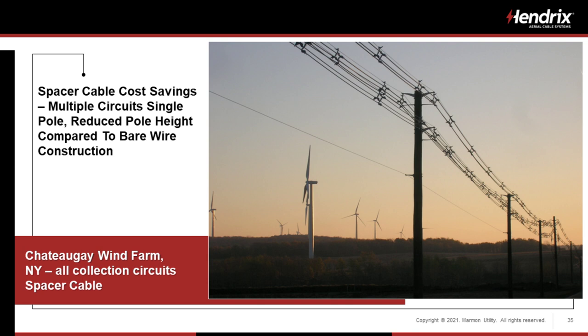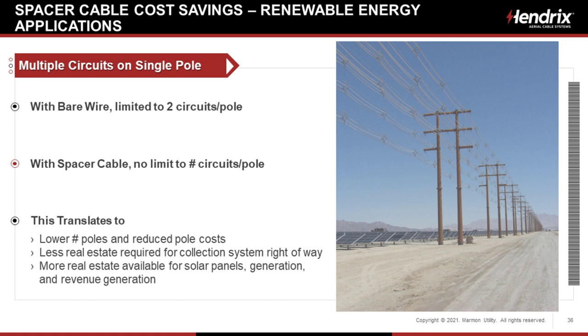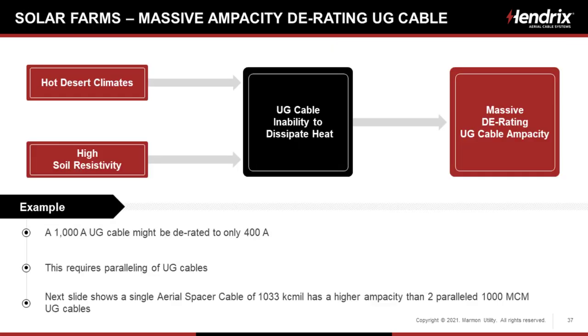Compare that to what we're doing. We put the same three circuits on a pole, probably less robust, and we've never had a problem with that, and it's very low profile and very easy to work. Again, with bare wire, I say you're limited to two circuits per pole. You can put three circuits like they did in a couple of slides earlier, and you're begging for trouble. Nobody will work on it. With spacer cable, there are no limitations to the number of circuits per pole, 8, 9, 20, whatever you want. This translates to a lower number of poles, reduced pole costs, less real estate required for collection system right-of-way, more real estate available for solar panels, generation and revenue generation.